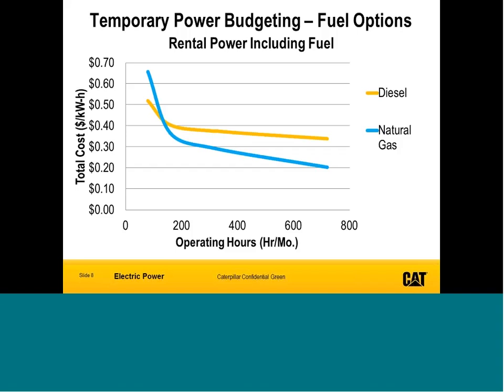The upside of the gas generator is that you do not have to deliver fuel. So if it's an environment where roads are impassable, trees are down, flooding, whatever it may be, and you can't get a diesel truck in to refuel your genset, but the pipeline is up and running, then you would have ongoing uninterrupted service at your facility. And that would be the advantage of going with a gas genset.